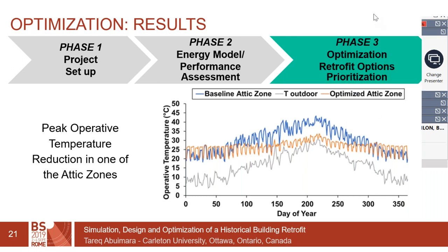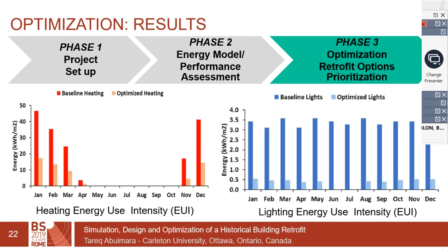Based on the optimization results, we were able to reduce the operative temperature in most building zones. As an example, we substantially cut the peak operative temperature in the attic, which was the worst case. We also cut the heating energy use intensity by about 69 to 70 percent, and the lighting energy use intensity by about 80 percent.